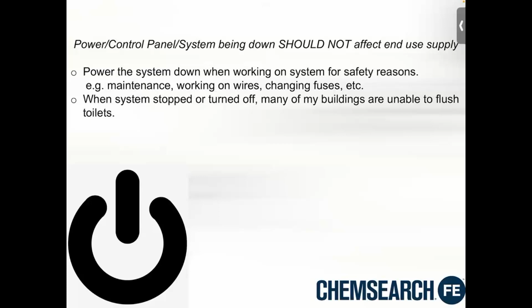I feel there's definitely a solution to this. All systems should be required to have diverter valves, whether manual or automatic, with the capability to bypass to domestic water with backflow protection. When you do that, the city water pressure would be enough to send water to the toilets. However, keep in mind, if you have a very tall building, you'd also need a separate booster pump station with its own control panel or VFD that doesn't rely on the rainwater system at all. Because if the booster pump station's power were still connected to your reclaimed water system control panel, and that panel went down or had to be turned off, you still wouldn't be able to flush the toilets.